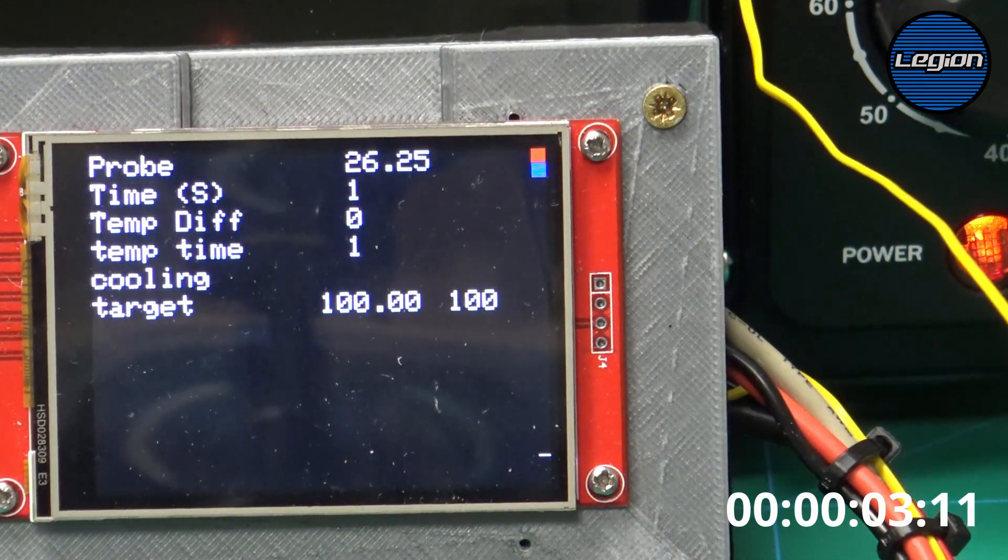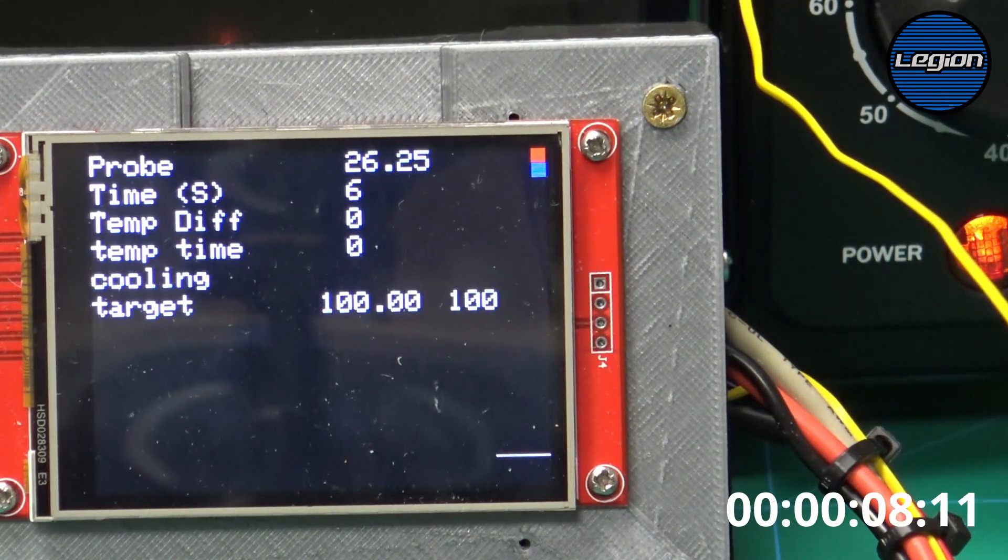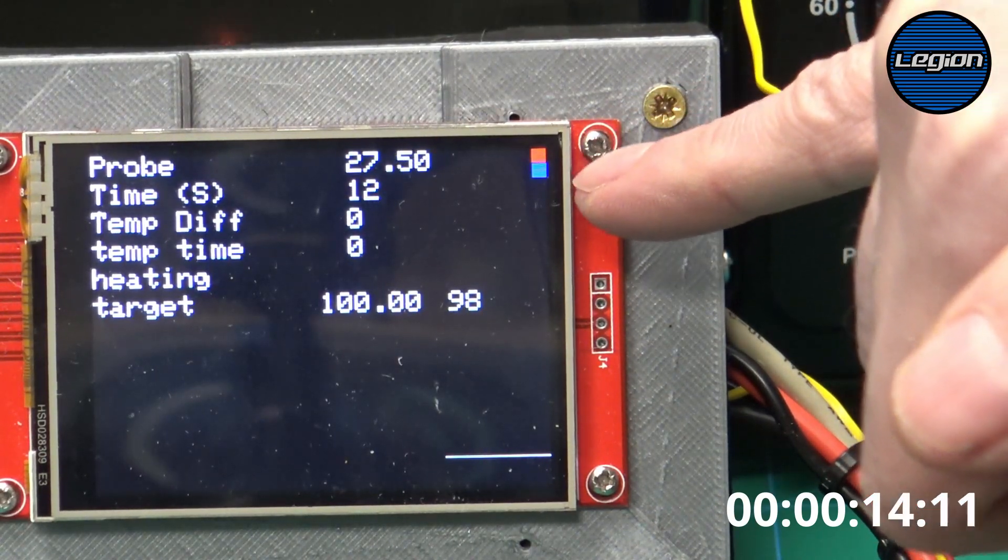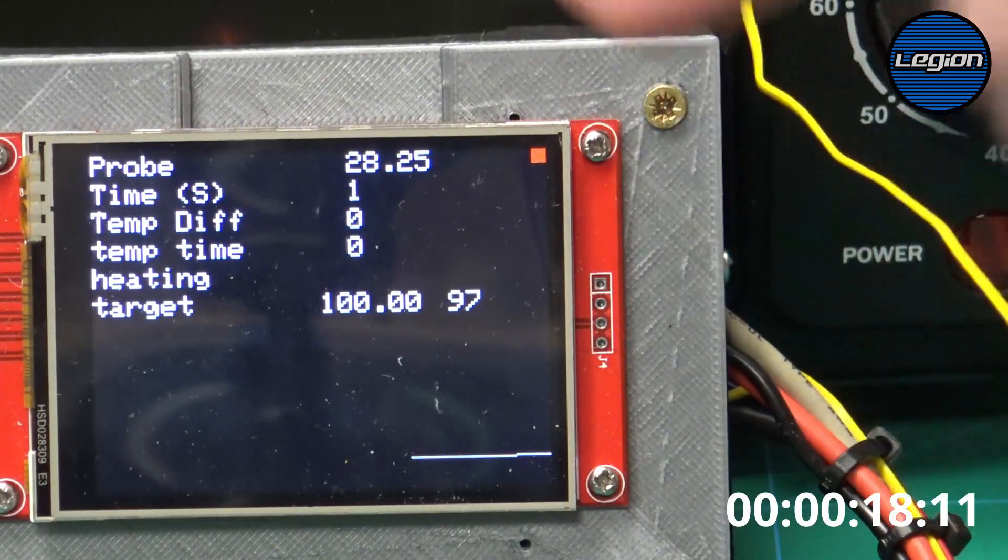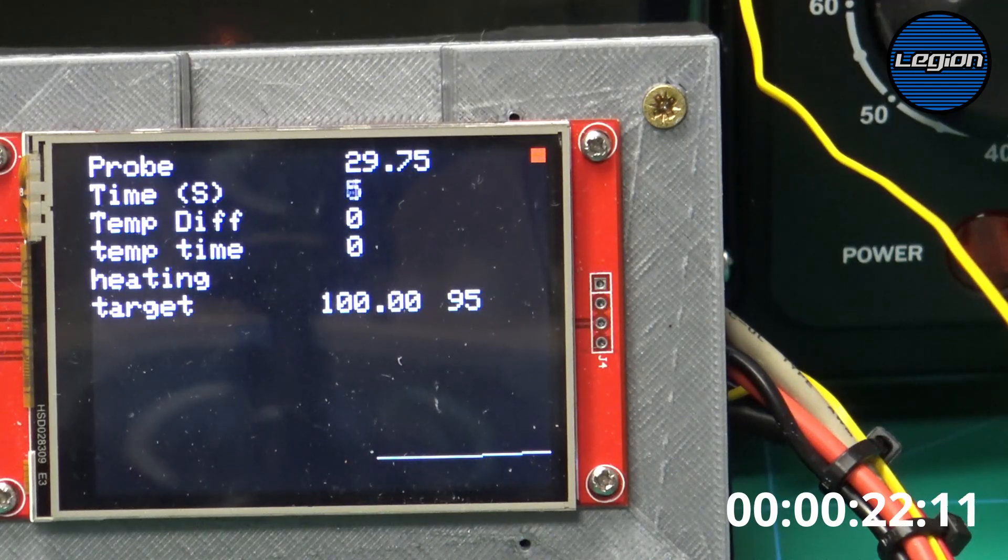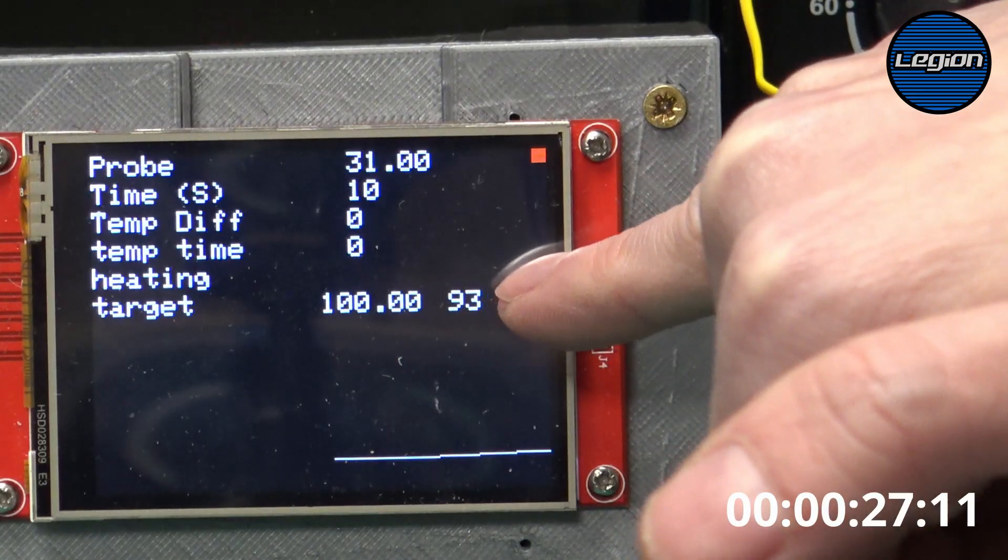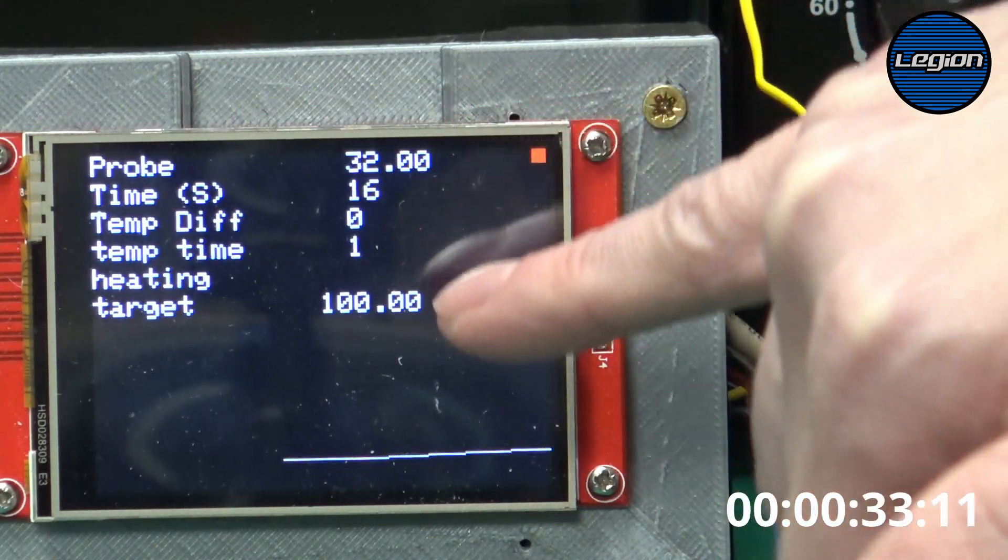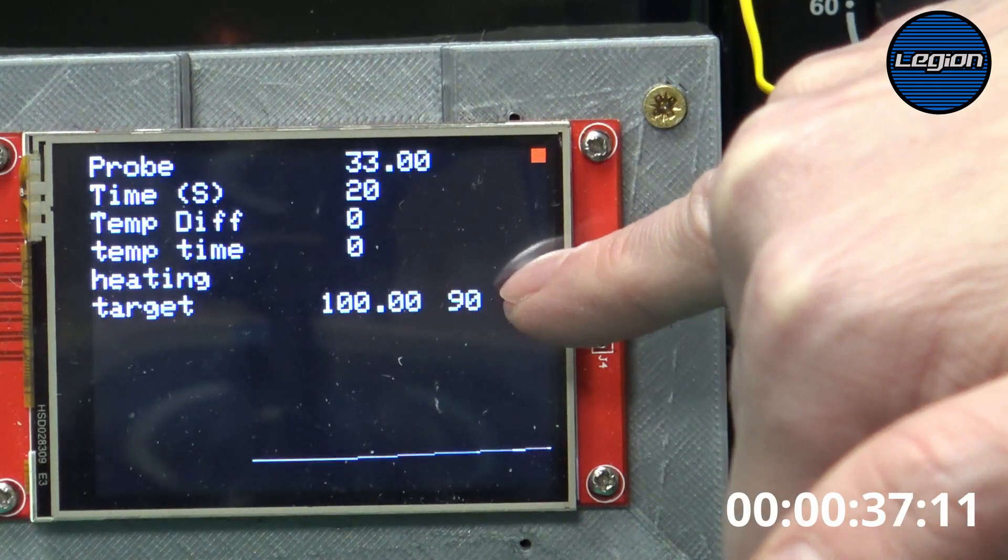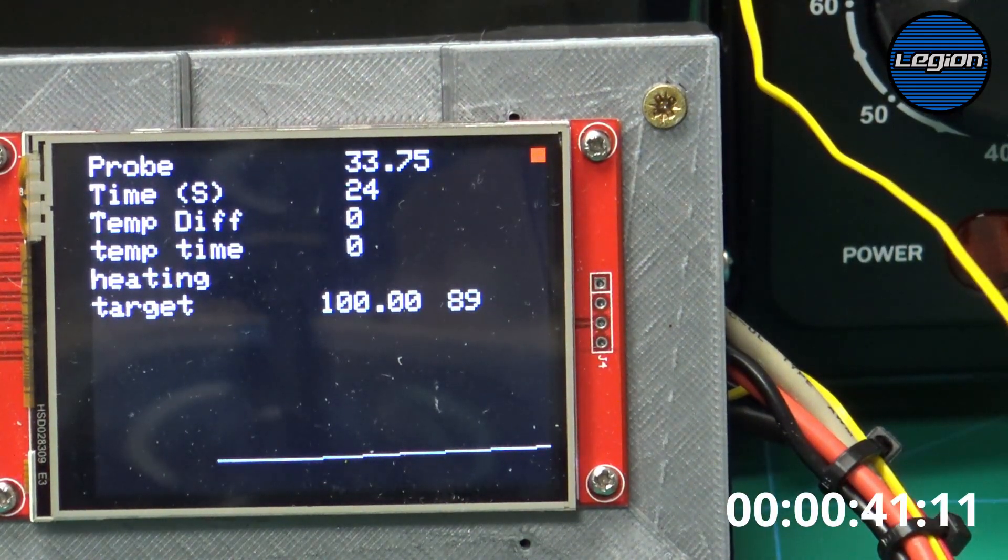So we're going to boost up to a hundred. So now this is working we can see they've got the power light on. So just here we have two indicators. Blue means that the element is on and then the color at the top determines what zone that we are in. So at the moment we are red and that is represented by the percentage that we have just here. So our target is 100 we're currently at 31 and depending on what percentage range that we are in it will change how long it heats for.